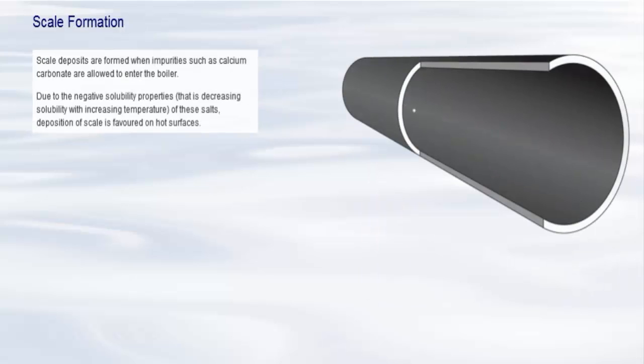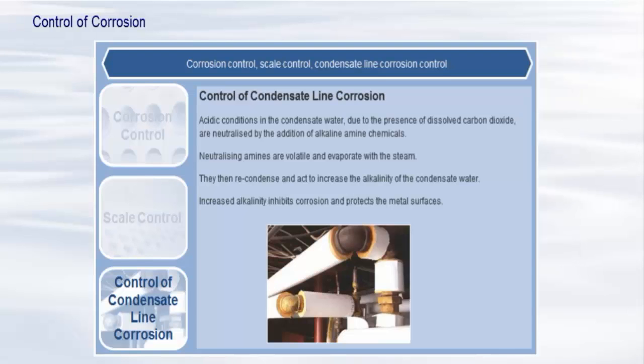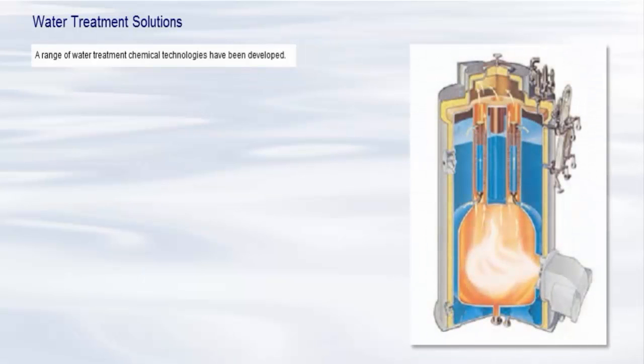Scale deposits are formed when impurities such as calcium carbonate are allowed to enter the boiler. Due to the negative solubility properties, that is, decreasing solubility with increasing temperature of these salts, deposition of scale is favored on hot surfaces. Scale deposits form hard and tenacious layers inside the boiler tubes. Such deposits will reduce heat transfer efficiency, cause overheating and potential tube failure.